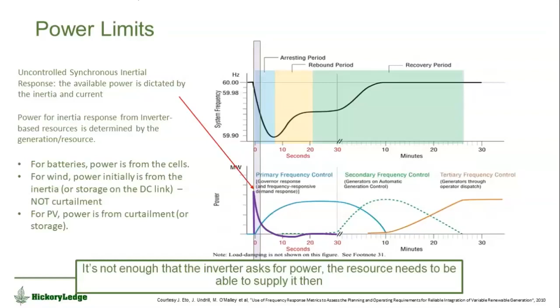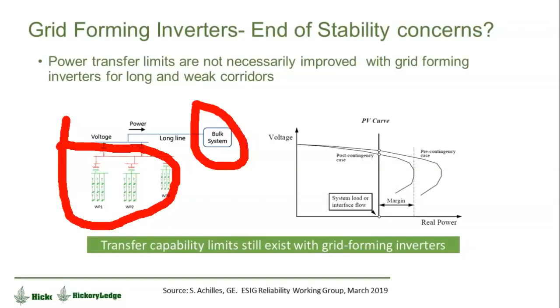The other thing for consciousness raising is that in this world here—I'll circle it—these guys can all be grid forming. I can have perfect control of the voltage of the sending end system, but if I try to push too much power into it, it's going to fail somewhere over here, and that's what the PV curves are about. We've spent time with many of you on the call looking at the reality that future modes of failure are going to look more like voltage collapses and transient voltage collapses than traditional loss-of-synchronism type problems. So that stability limit is still there.